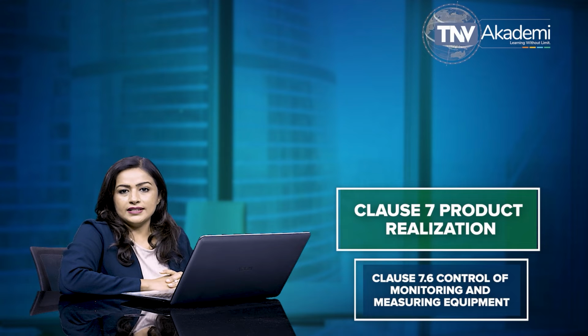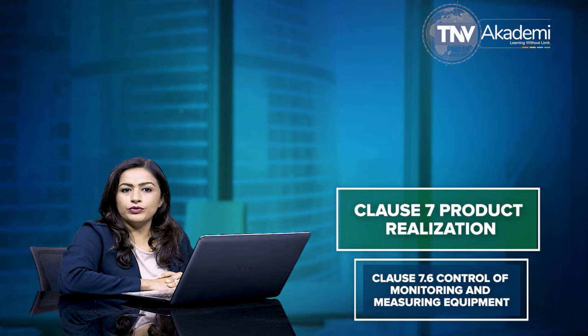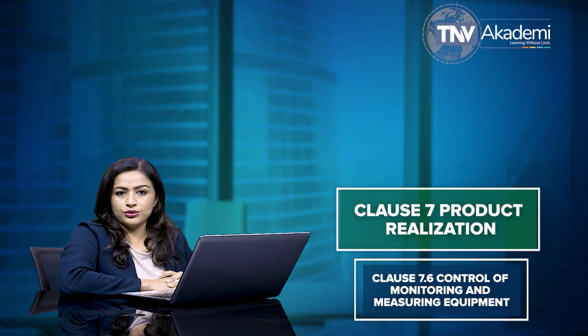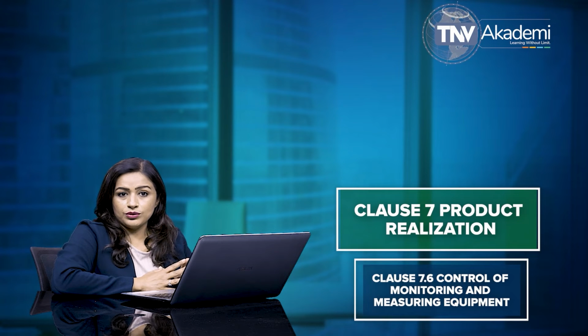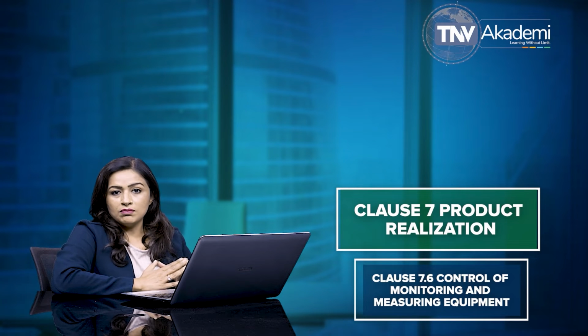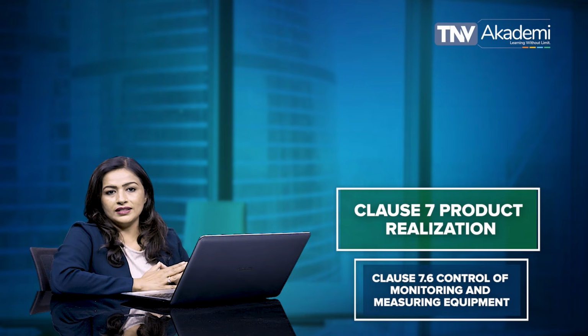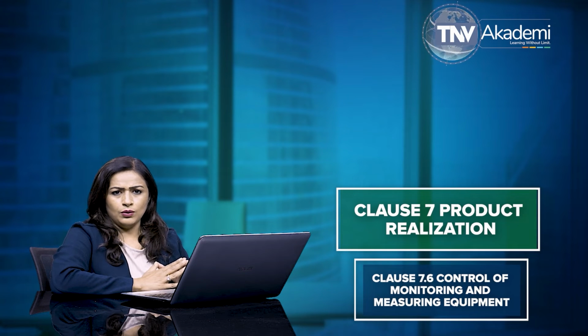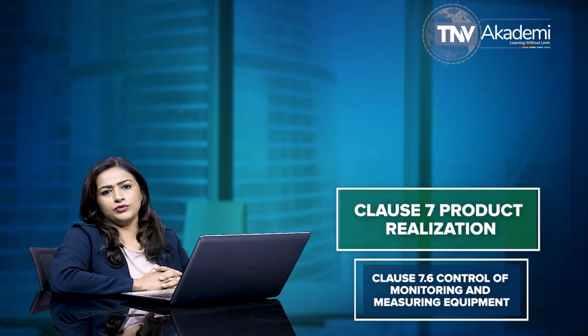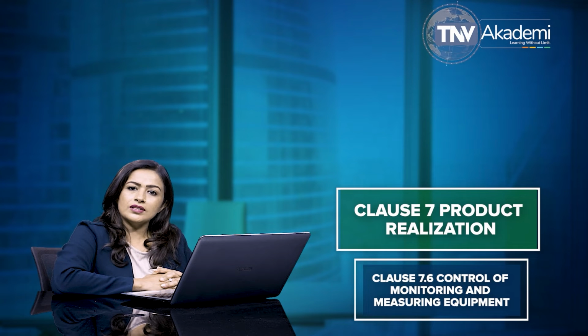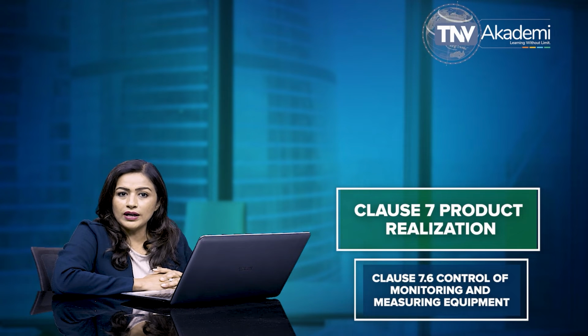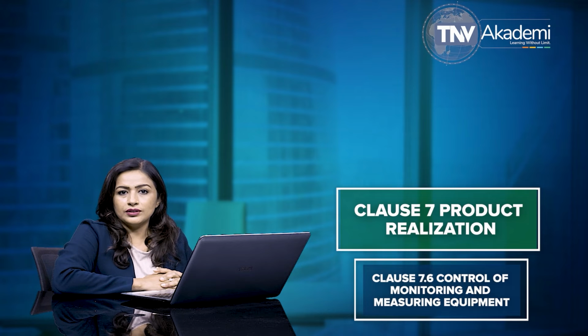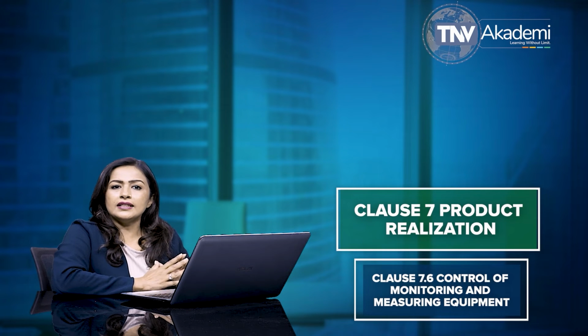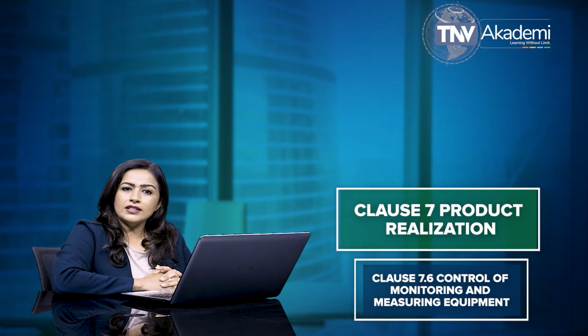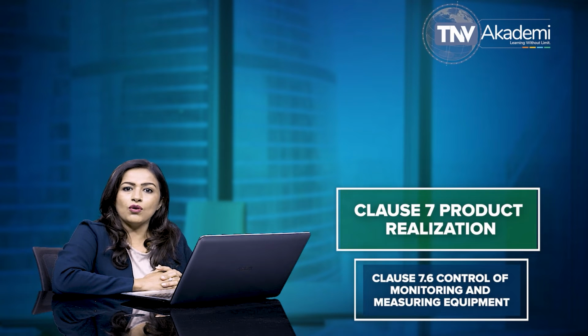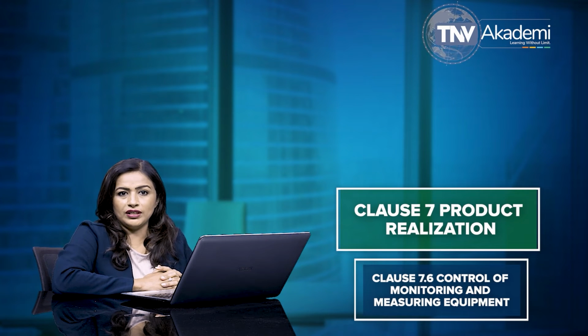Subclause 7.6 states that the organization is required to perform calibration or verification in accordance with documented procedures. In addition, the organization must assess and record the validity of the previous measuring results when the equipment is found not to conform to requirements. As per this clause 7.6, the organization is required to take appropriate action in regards to the equipment and any product affected. The organization is also required to maintain the records of the results of calibration and verification.